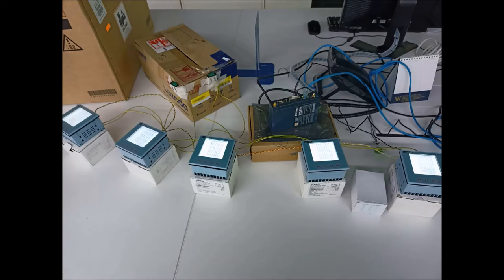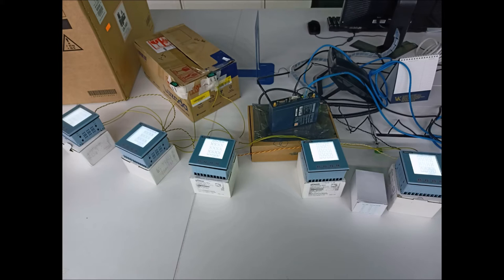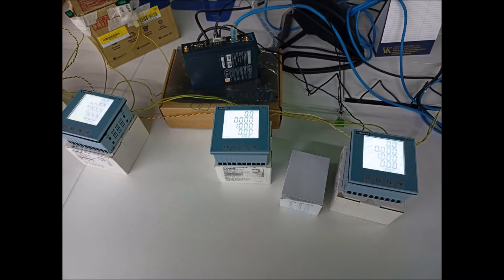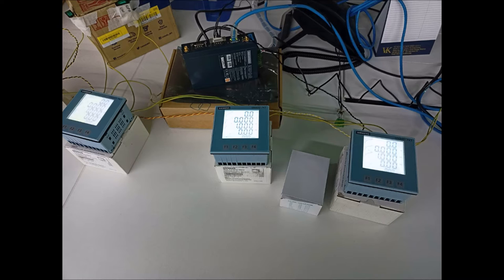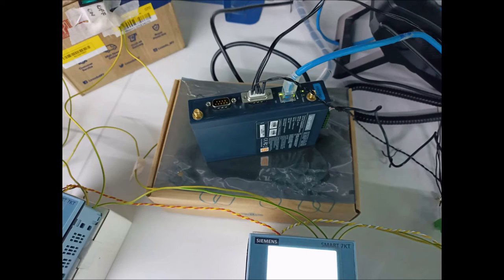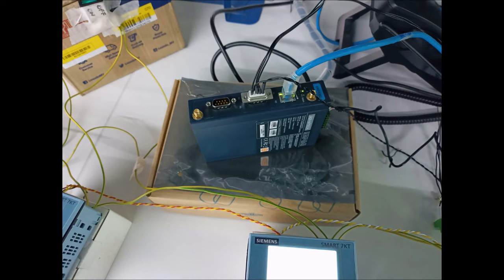Before I begin the project demonstration, just a quick overview on how the devices are set up in the server. Here we can see there are a total of five digital power meter devices connected via daisy chain by using the cable RS-485, which is then connected to the wireless serial converter. Each of these devices has its own device ID such as 1, 2, 3 and so on. These devices are specifically used for measuring power usage such as current and voltage. How the Gateway facilitates communication with the device is by using the Modbus protocol, which I will explain later.